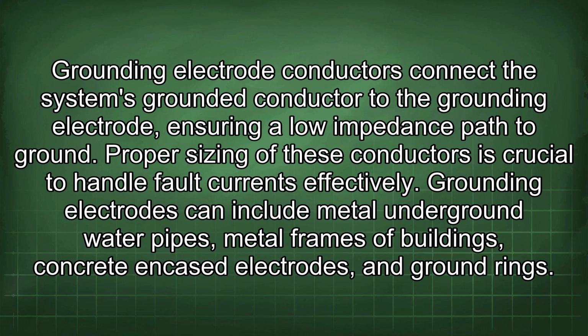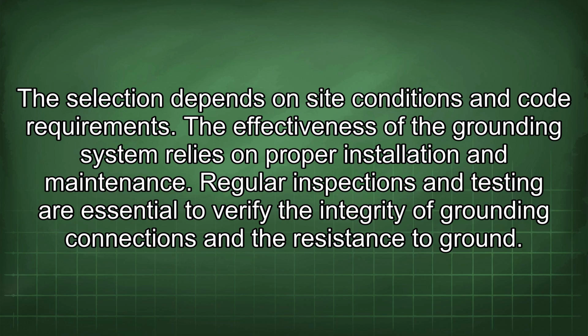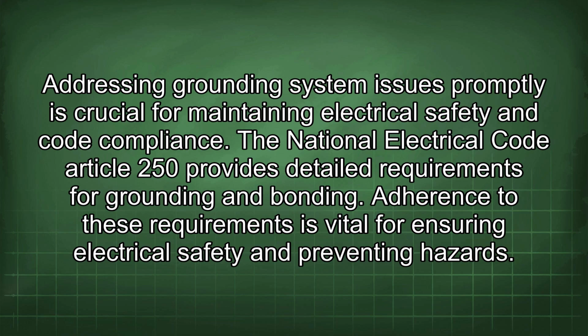Proper sizing of these conductors is crucial to handle fault currents effectively. Grounding electrodes can include metal underground water pipes, metal frames of buildings, concrete encased electrodes, and ground rings. The selection depends on site conditions and code requirements. The effectiveness of the grounding system relies on proper installation and maintenance. Regular inspections and testing are essential to verify the integrity of grounding connections and the resistance to ground. Addressing grounding system issues promptly is crucial for maintaining electrical safety and code compliance.